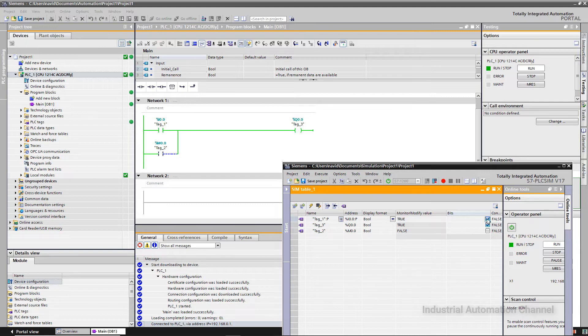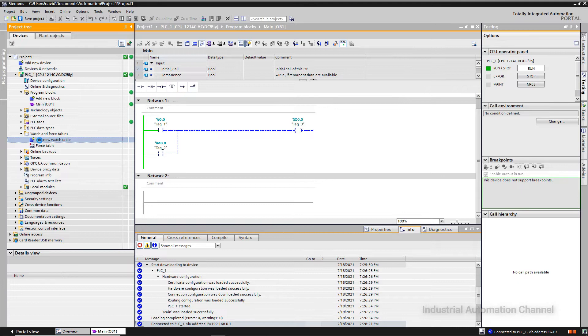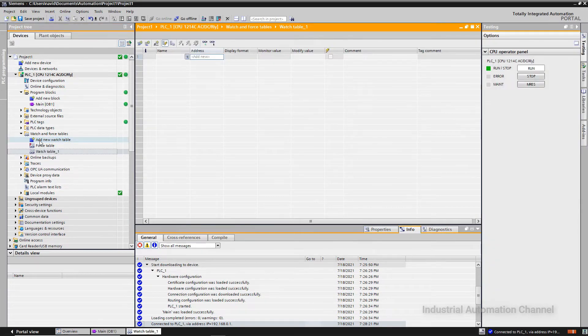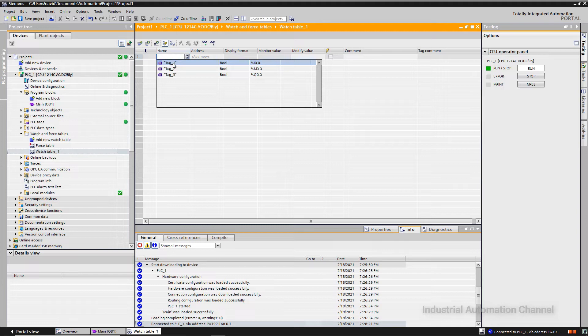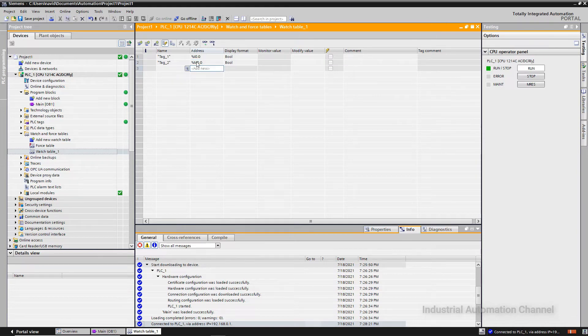Another way to see the status of our inputs and outputs is the watch table. You can find it here — open Watch and Force Table, then add a new watch table. You can add one or more tables. We can add our inputs using their name or address. If you click on the little box here, you will see all your tags and can choose them. Alternatively, you can write the variable name in the name box or the variable address in the address box.